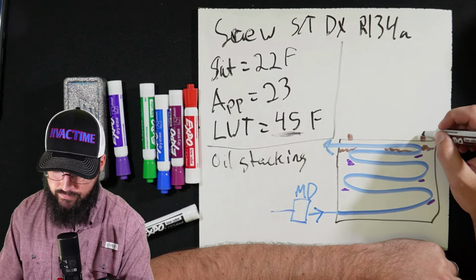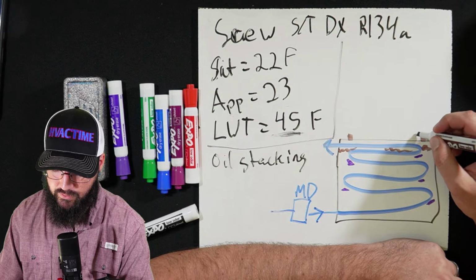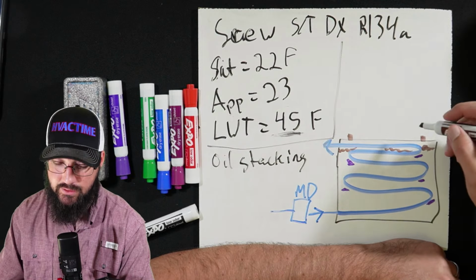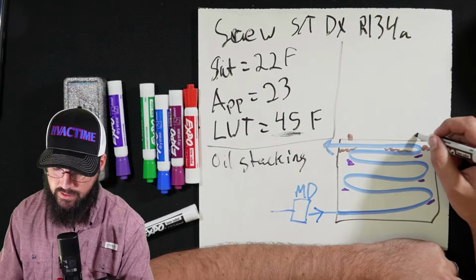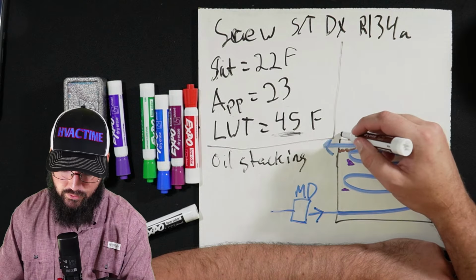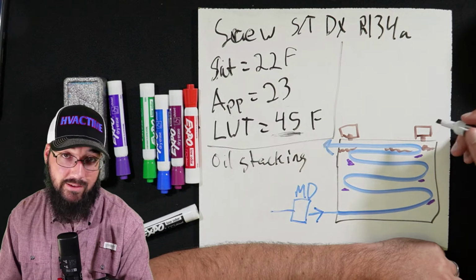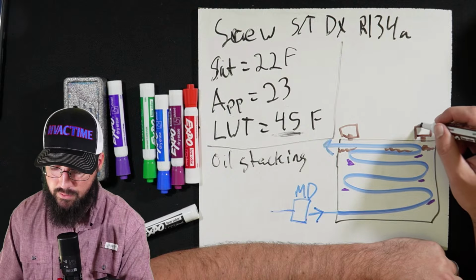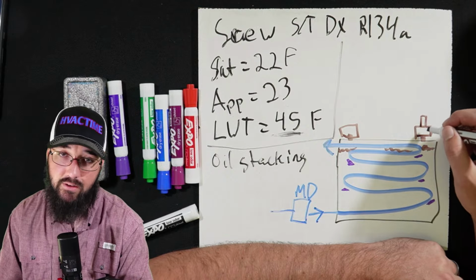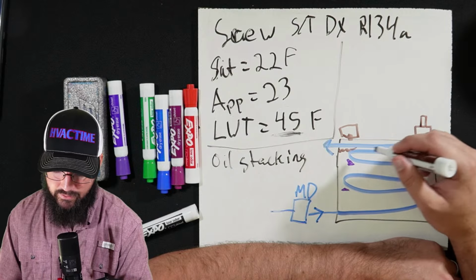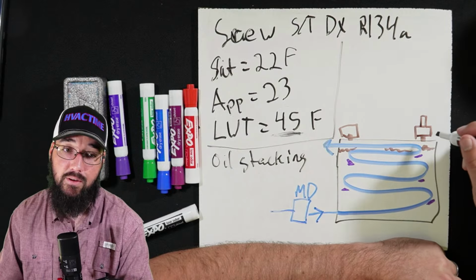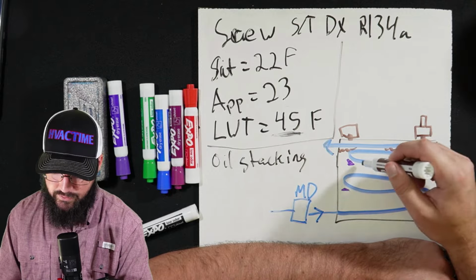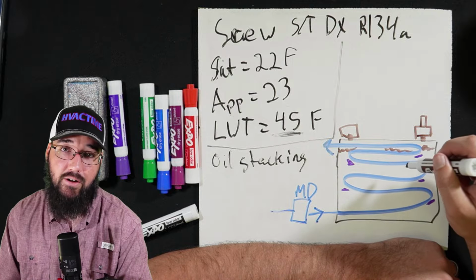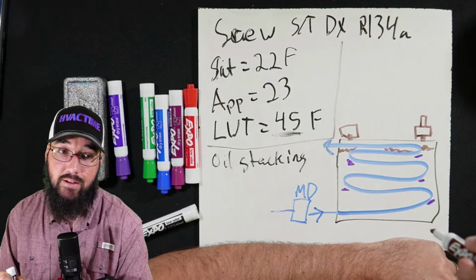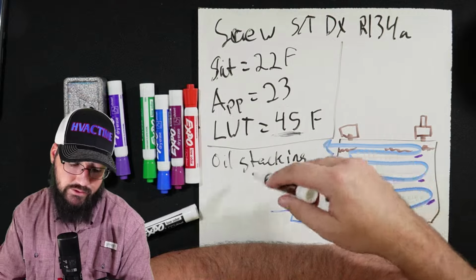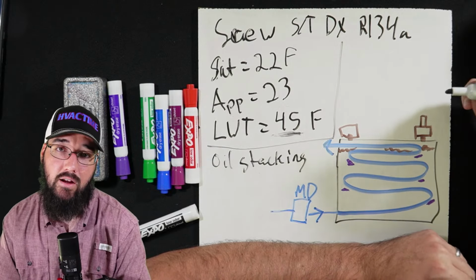So my preference is, if I'm thinking this is the case, isolate the water side on that evaporator and then open or remove one of these plugs, at least one of them, and I like to either put a ball valve so I can manually bleed it or put an air bleeder there to try to make sure the air stays out of the top of this, because if the top side of this evaporator does get air stacking, it will create these exact conditions. Similar to the oil stacking, it'll cause a lack of heat exchange.